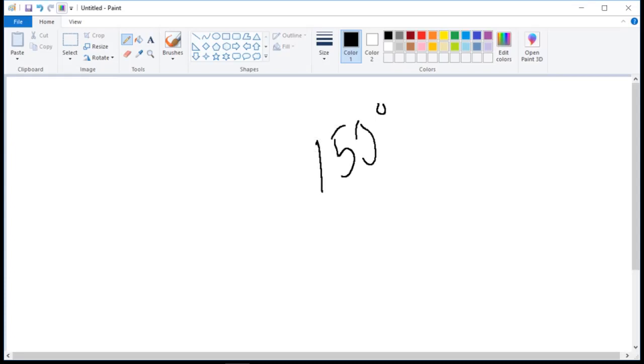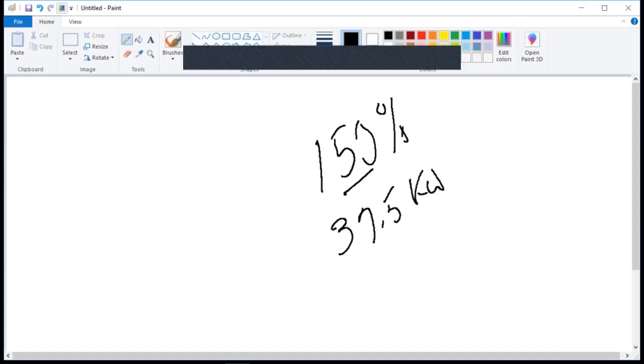150%. So if I've got 25 kVA normally, that's the 100%. If I need to go to overload, I can add 12.5 to that, so that's 37.5 kW, kilowatts.